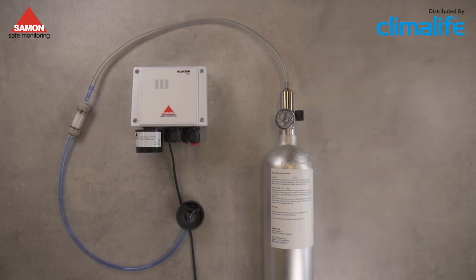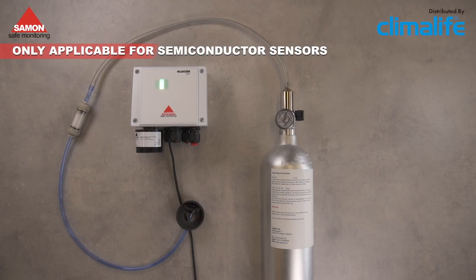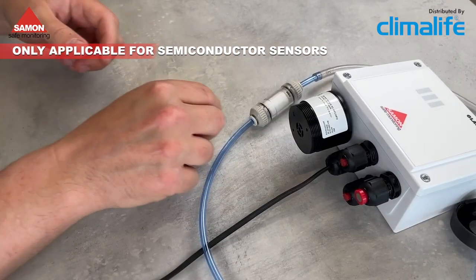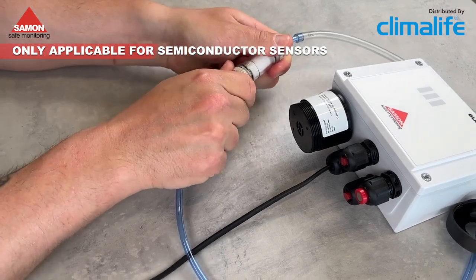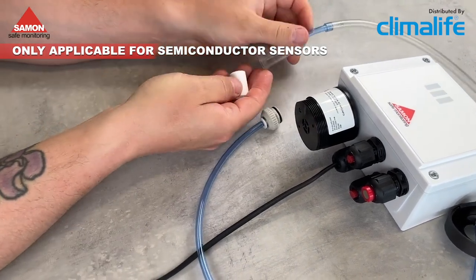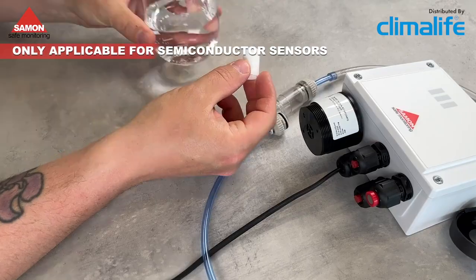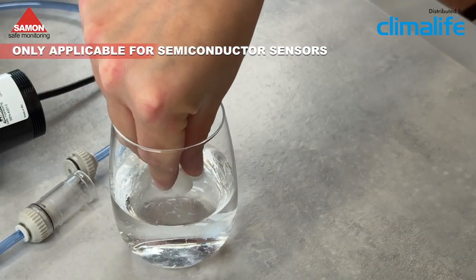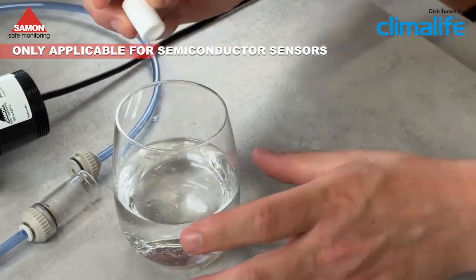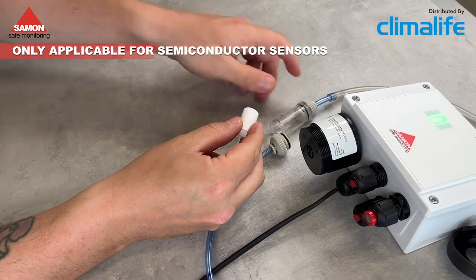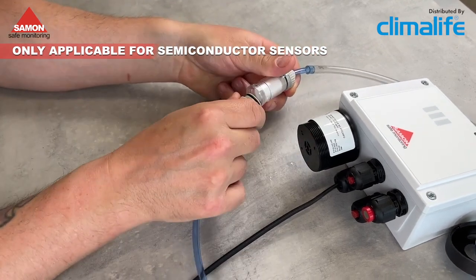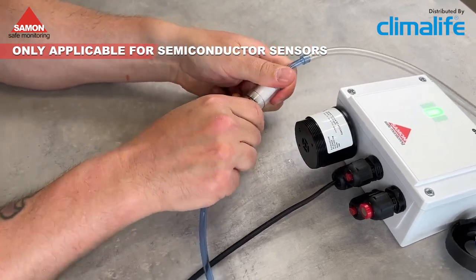Before you mount the calibration kit on the sensor, it is important that the filter is moist if you are calibrating a semiconductor sensor. For other sensor types, it is not necessary to moist the filter. Remove the filter by pressing the lever and then detaching the two parts. Immerse the filter in a container filled with tap water for a few seconds. Place it back in the previous position and close the filter.